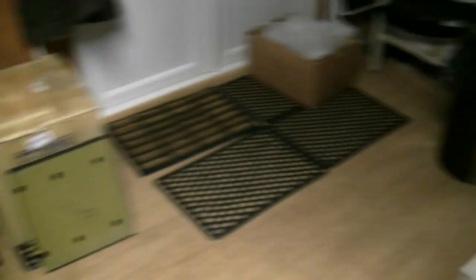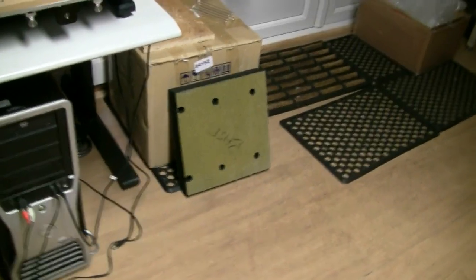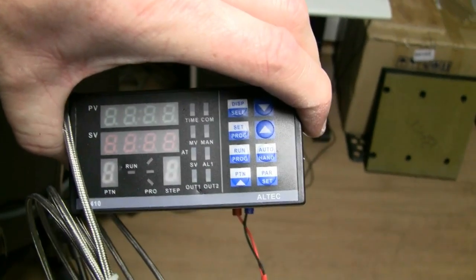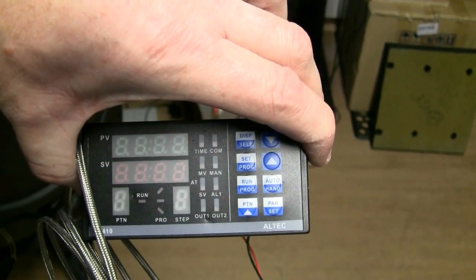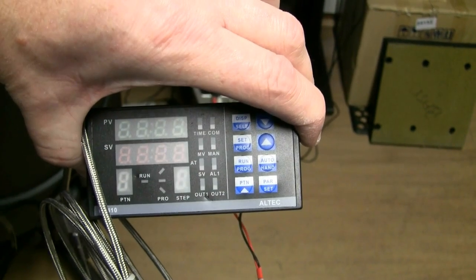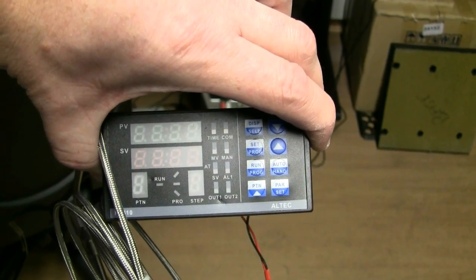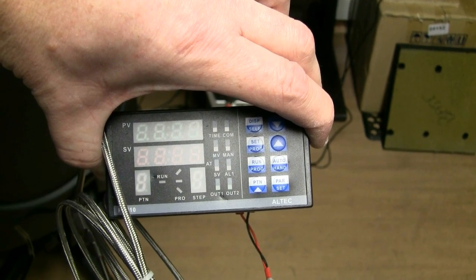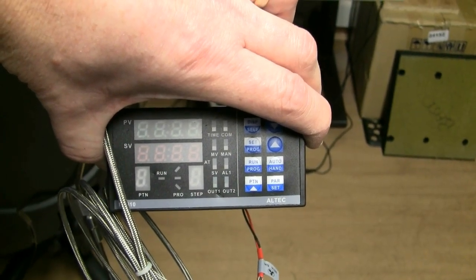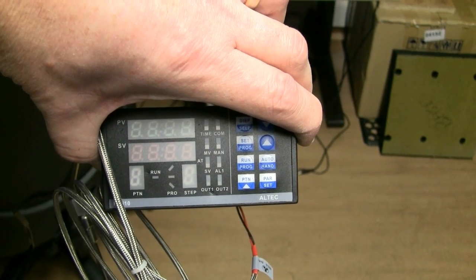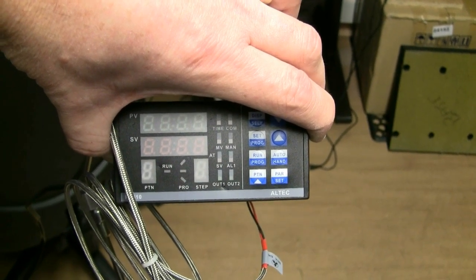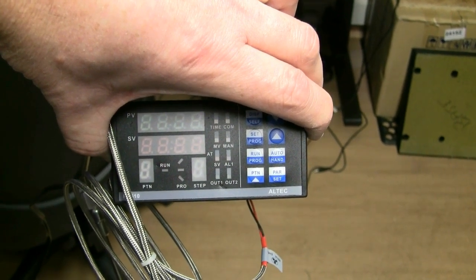The controller, there we go. This is an Altec PC410 multi-channel multi-sequence PID based temperature controller. You can have up to ten programs, each eight segments long with a programmable ramp set point and dwell time. That's quite neat, it pretty much does everything I think you need to do. It also has a self calibration or a learning mode.